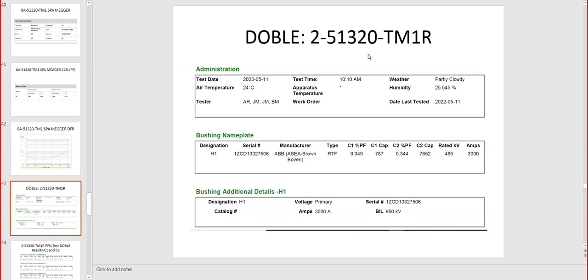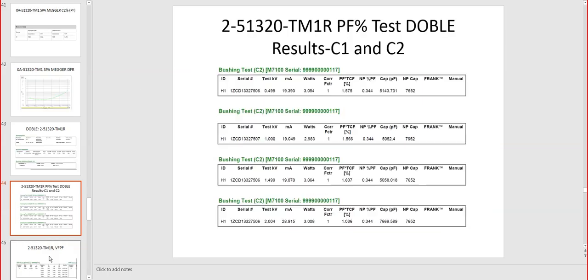for the second transformer, so this is unit 2, we got H1 again, nameplate data, and then bushing additional H1. That's all nameplate data for this transformer. And for the transformer unit 2, we got these results for C1, C2. So if we look here, we got capacitance and C2 test for 500 volts, 1000 volts, 1500 volts and 2000, similar to what we did for the previous one, to compare one transformer to the other.